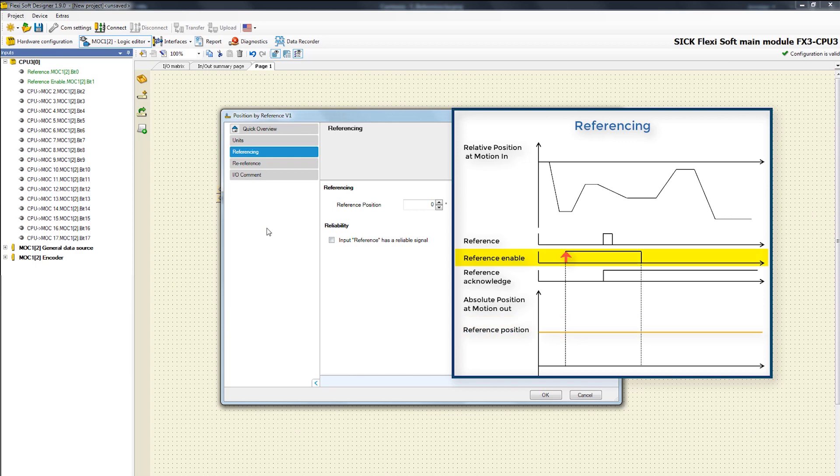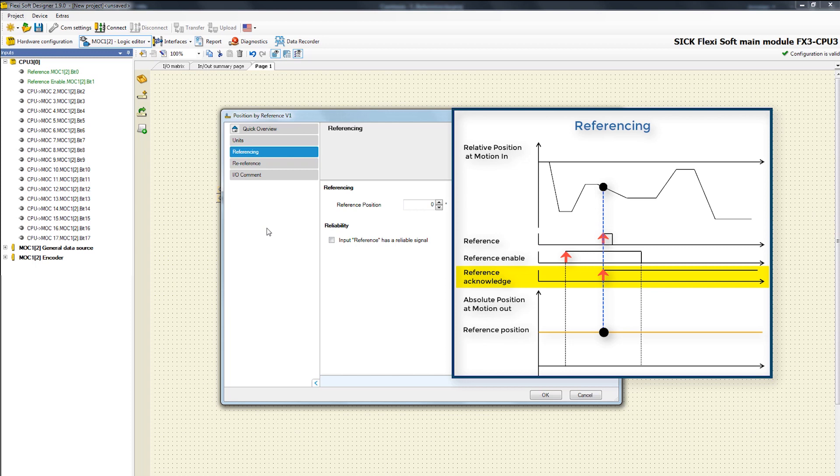If there is a high signal at the input reference now during an active reference process, then the value for the absolute position is set to the defined start value. In this case the output reference acknowledge is set to one and the function block starts calculating the absolute position internally by using the relative position data at the input motion in.